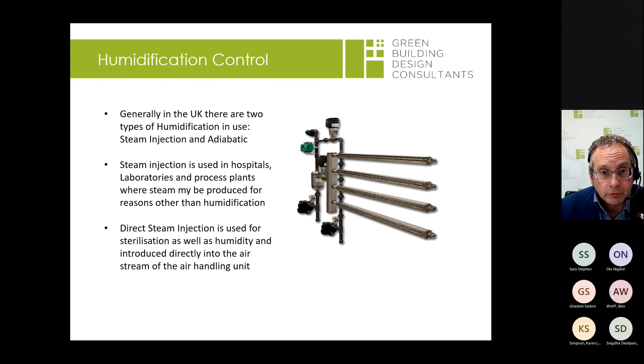That sort of direct steam would now almost certainly want to have sterilised water with it. So there's the cost now of not providing just mains water like we used to do in the 80s and having all that scale problem, but having cleaned water, usually RO water or deionised water, through a set-up plant that takes all of the bugs out and takes all of the scale out and any impurities, so that it's very clean water. Which again is another load of equipment, another cleaning process, and another piece of plant to site on the roof, and another piece of plant you've got to buy. But that's how the steam humidification would work.